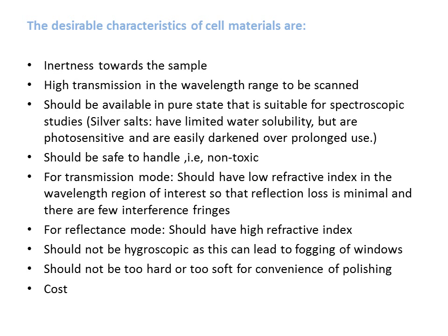So here too you have to select a material which has high transmission to the IR radiation. It should be inert, it shouldn't chemically react with the sample. It should be available in the pure state for suitable spectroscopic studies.